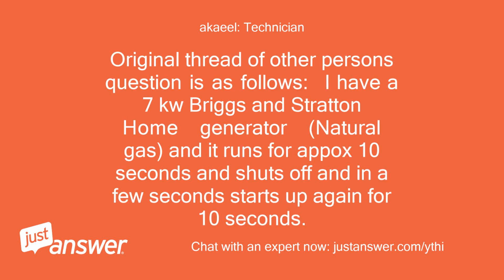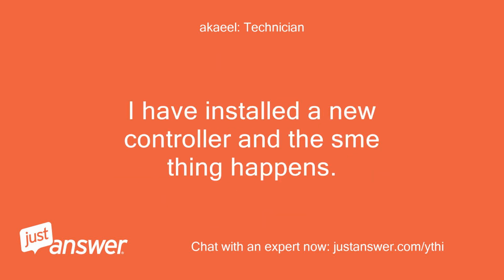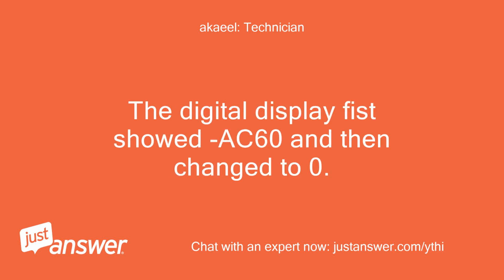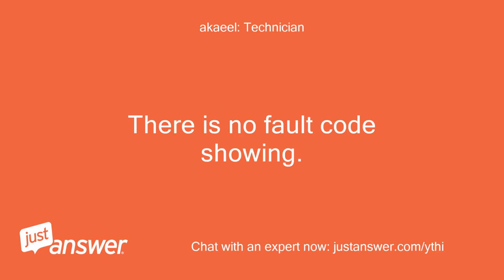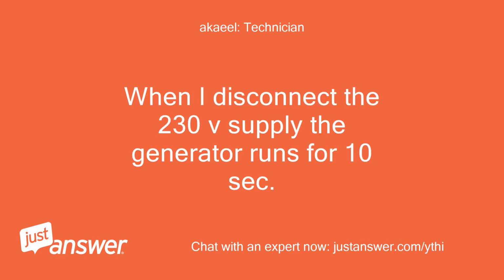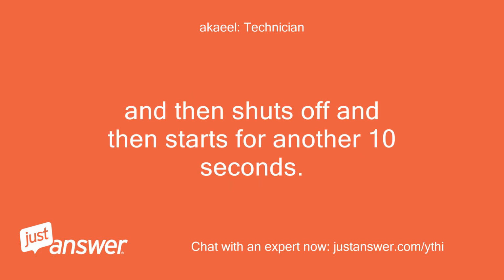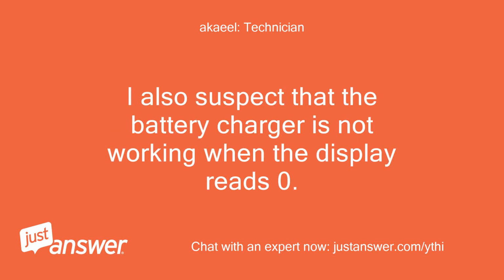Original thread of other person's question is as follows: I have a 7 kW Briggs and Stratton Home generator, natural gas, and it runs for approximately 10 seconds and shuts off, then in a few seconds starts up again for 10 seconds. I have installed a new controller and the same thing happens. The digital display first showed A.C. 60 and then changed to 0. There is no fault code showing. When I disconnect the 230V supply, the generator runs for 10 seconds, then shuts off and then starts for another 10 seconds. I also suspect that the battery charger is not working when the display reads 0.